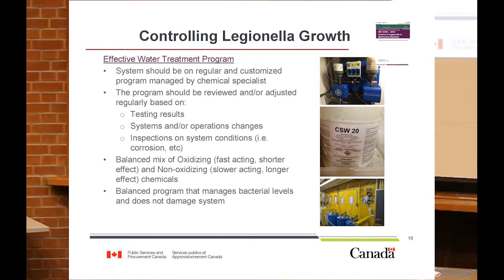It can add nutrients, but it can also provide areas for the bacteria to be sheltered from any chemical treatment. So the program needs to be adjusted based on testing results that are done regularly by our chemical treatment specialists, looking at the pH of the water and conductivity, to name a few. And then also inspections based on what they're seeing in terms of the system itself. Is there any corrosion buildup or any biofilms?